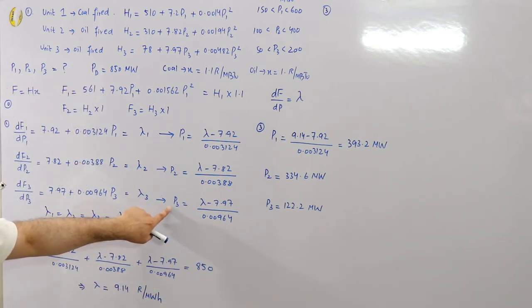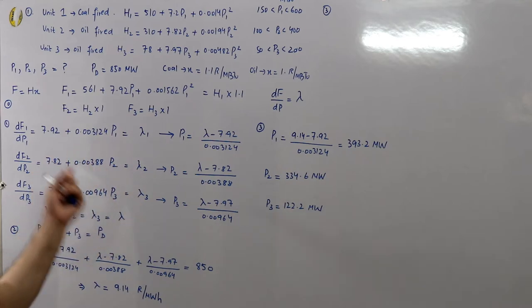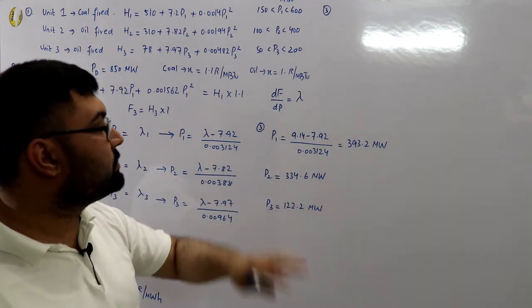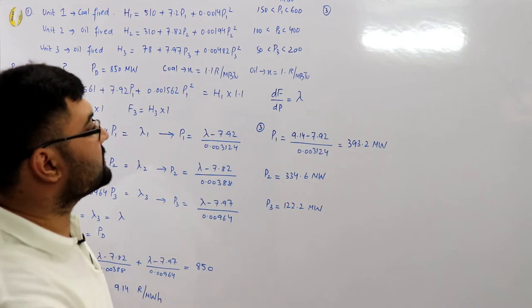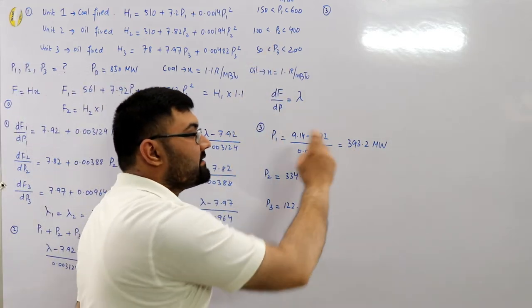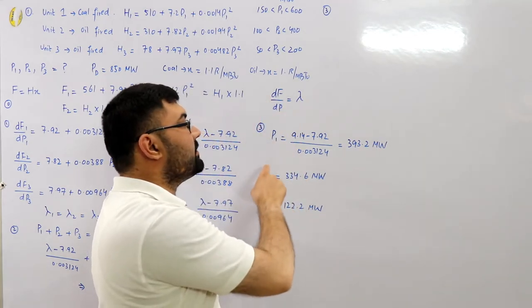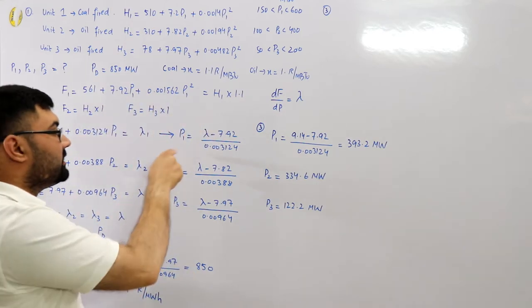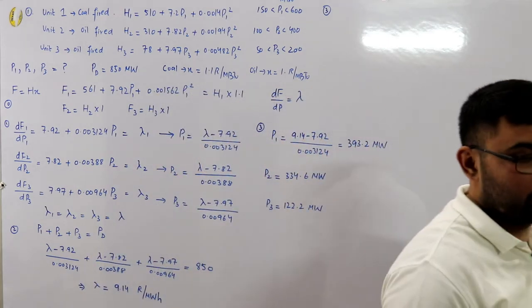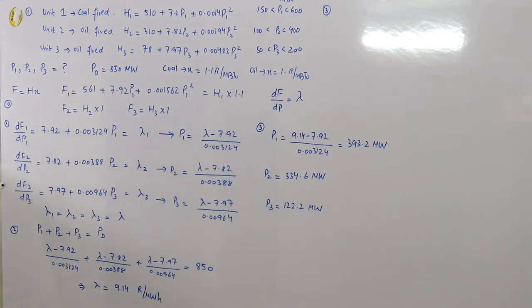If a value violates the economic limits — for instance if p3 were less than the minimum limit of 150 — you fix p3 = 150, then find lambda from the remaining units, and recalculate p1 and p2. If a value exceeds the maximum limit, say p1 > 600, set p1 = 600 and recalculate lambda, p2, and p3.